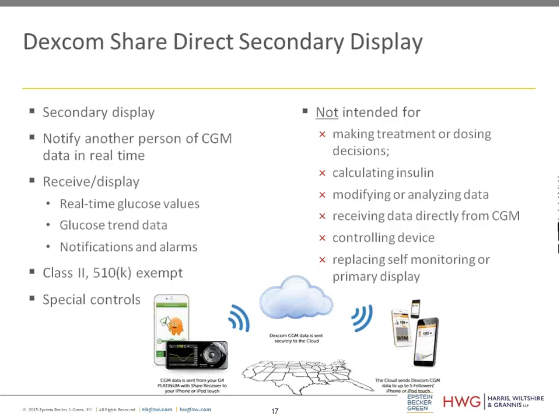But what's interesting and why this is important is that this went through the de novo process, and it was cleared as a Class 2 510K exempt product. Historically under the existing or prior model, it most likely would have been considered Class 3 because it was an accessory to a CGM. Now it's Class 2 and 510K exempt, meaning manufacturers of devices which fall within this same category and definition do not need to submit a 510K in advance. They do need to follow special controls, but that is a significant reduction in the regulatory burden for manufacturers.